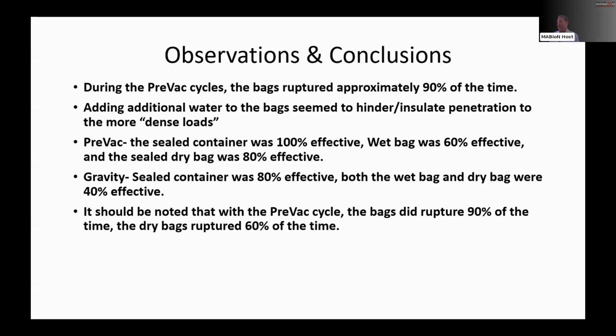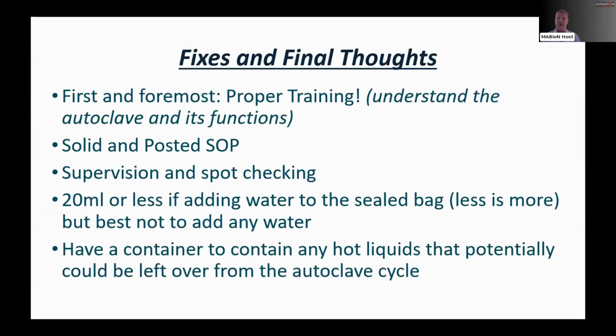It's going to sense that steam in that bag and on your chemical strips. You're not going to get it. You're just not going to get it unless you're getting your BIs. If you're not putting BIs in there and you're using the test strips, please stop. As you can see, it's not working very well. So I want to get to some of the fixes.